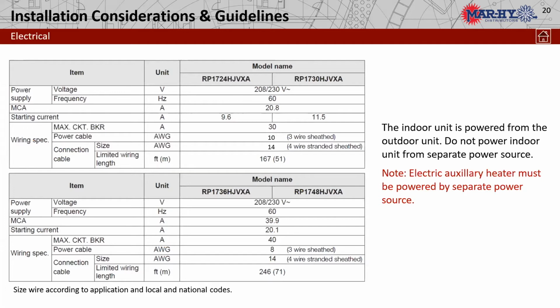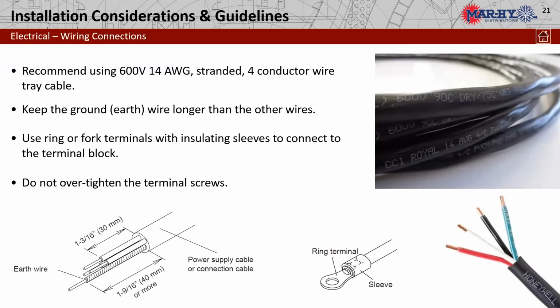Remember, we get our power for the indoor unit from the outdoor unit. So the wiring between the indoor and outdoor is what we already use for the mini splits. 14 gauge stranded, non-shielded, 4-conductor wire. Whatever it is you're currently using for your minis, that's probably what we're going to use for this application. They always say on this, leave your ground wire a little long. That's probably because the ground screw's a little bit further away than the actual lug for the power.